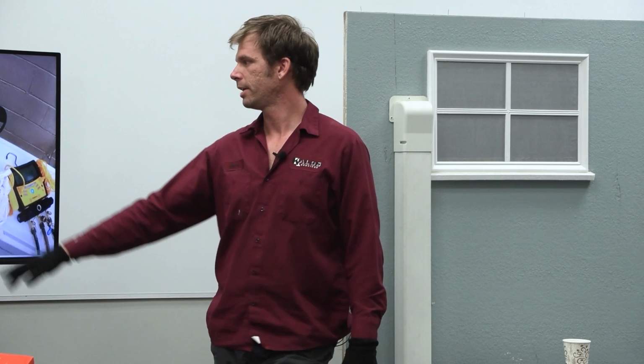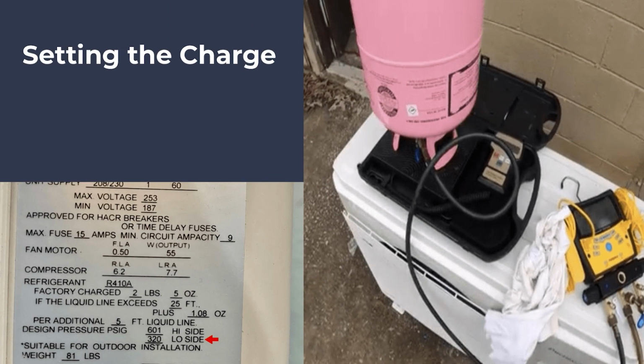Pressure testing after you've made your perfect flare is still really crucial and important. So just actually getting the nitrogen up above 300, around 400 psi is good, because those flares are going to be in heat mode, and your psi is going to be pretty high in heat mode on all of those flare joints. And if you actually look at the data tag, they have your low side, high side pressure, design pressure on here.